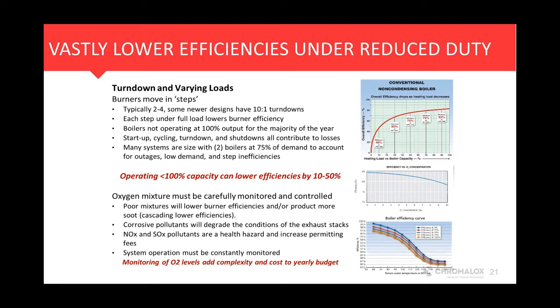You also have the oxygen mixture, a huge part of fossil fuel-fired systems. If the oxygen isn't regulated correctly, you might have poor combustion, leading to lower efficiency, or things not combusting at all, sending fuel right through the exhaust. That can create corrosive components, which from a pollution control and emission permitting standpoint becomes a very big problem. So you have to make sure you have the right controls in place for those systems to operate.